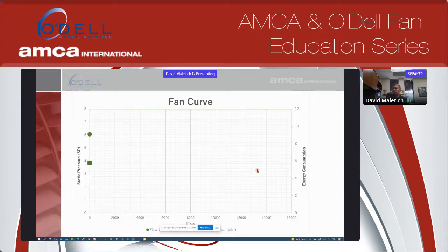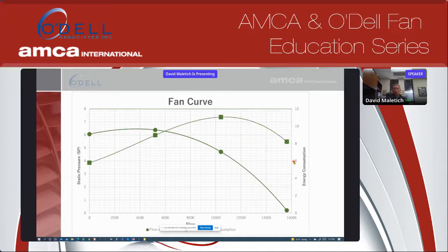You probably saw this in Bill's presentation a little bit earlier, Bill Howard, in that when you look at a fan curve, pressure is usually on the left-hand axis, flow is usually on the bottom, and energy consumption is typically on the right-hand axis. When we first test a fan, we close off all the nozzles, pressurize the chamber, and record the energy or the work that the fan's doing. In this case, the little square dot here is energy consumption. The round dot here is static pressure versus flow. And the fan's producing about 6 inches of static pressure, consuming about 6 brake horsepower. And we just simply open up the nozzles until we have enough points to create a fan curve.